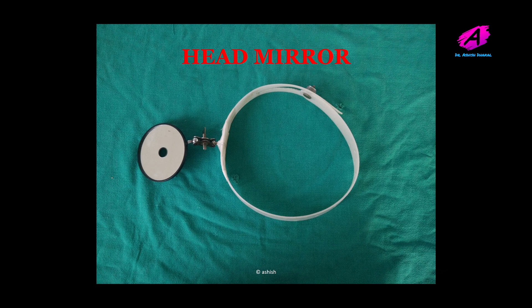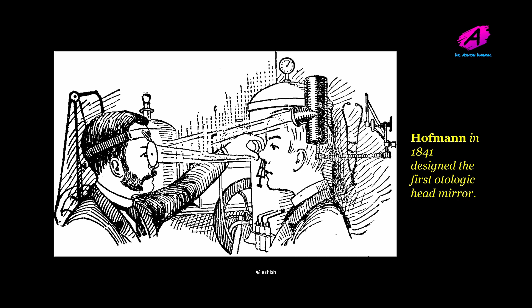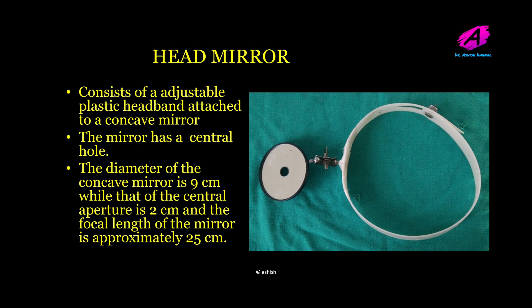This is another instrument, the head mirror. Hofmann in 1841 designed the first otologic head mirror. The head mirror consists of an adjustable plastic headband attached to a concave mirror. The mirror has a central hole. The diameter of the concave mirror is 9 cm, while that of the central aperture is 2 cm, and the focal length of the mirror is approximately 25 cm.